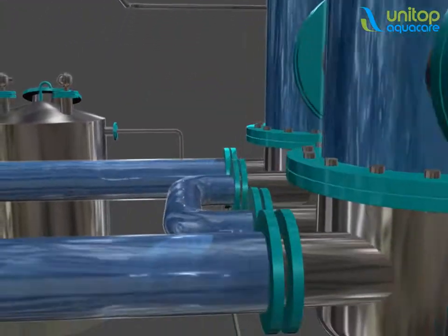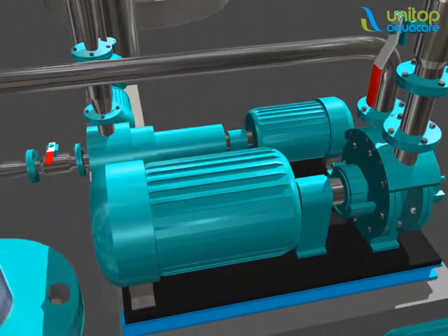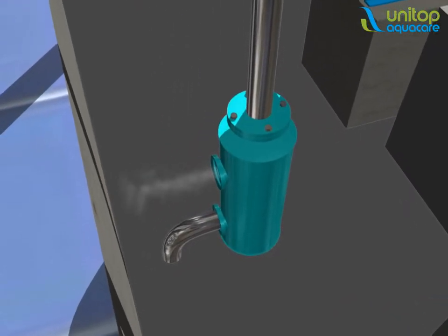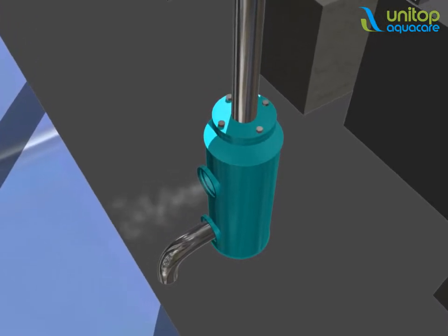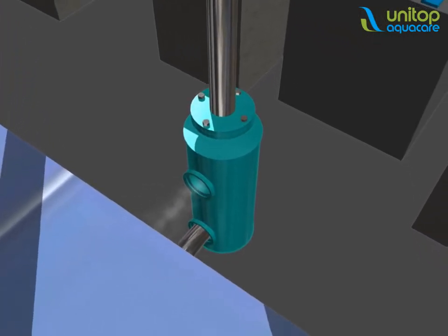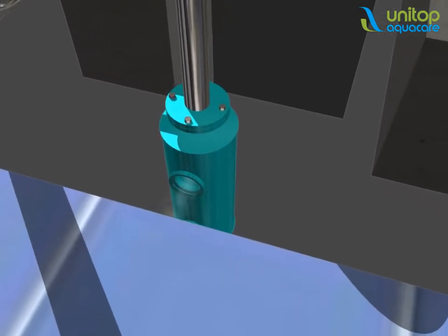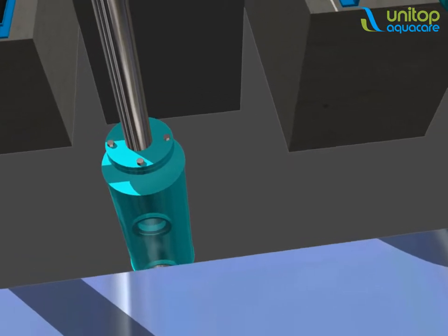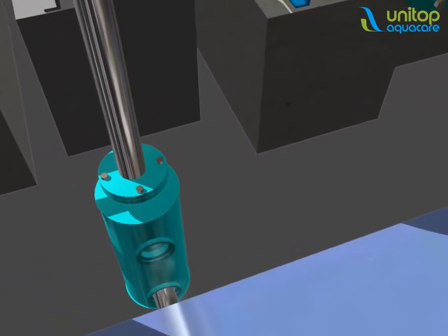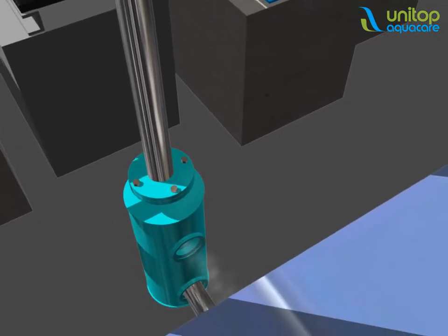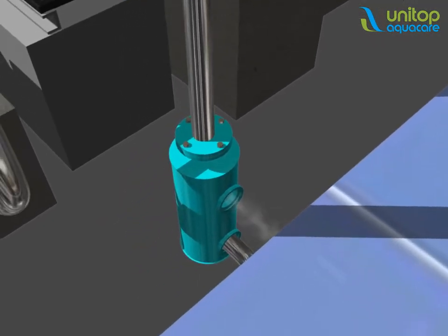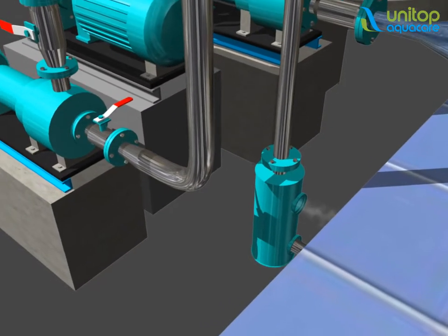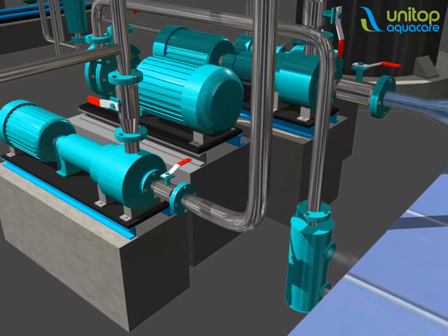Importance of applying the vacuum in the system. The air removal from the system is decisive for efficient working of the evaporator. Air has a low heat transfer coefficient and can drastically affect the evaporation rate. Also, leakage of air into the system results in lower vacuum, which in turn results in a lower temperature difference between each effect, resulting in a drop in capacity. This vacuum is produced by a water ring vacuum pump connected to the condensers.